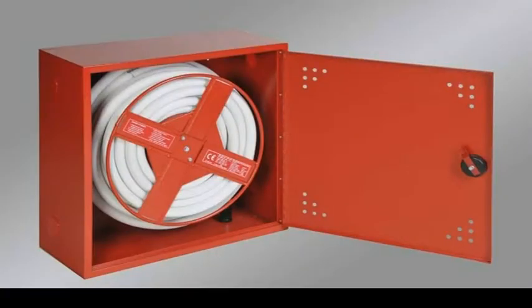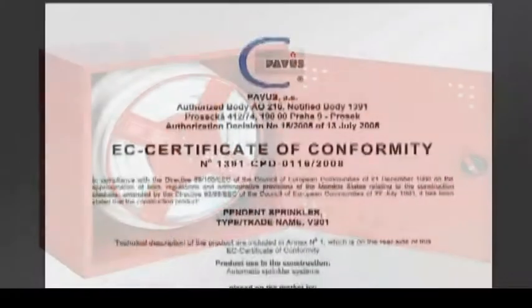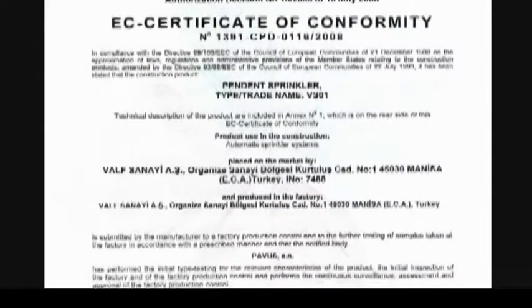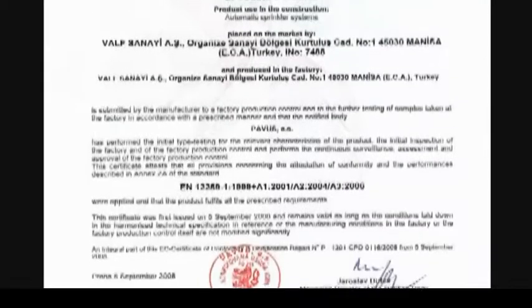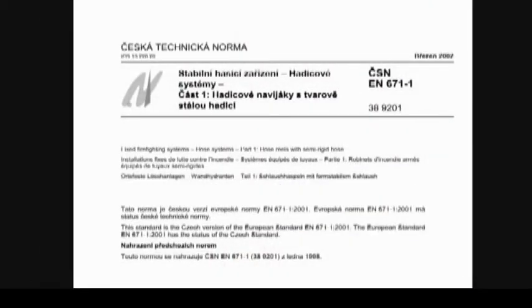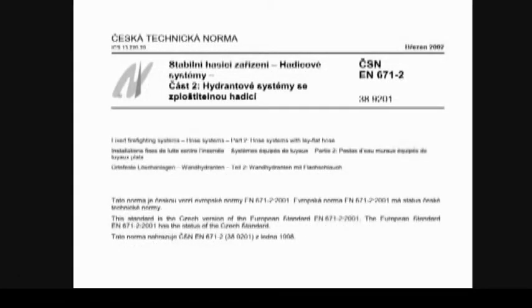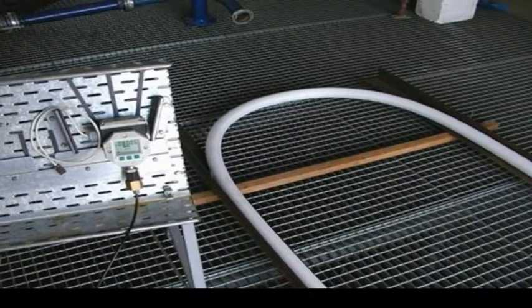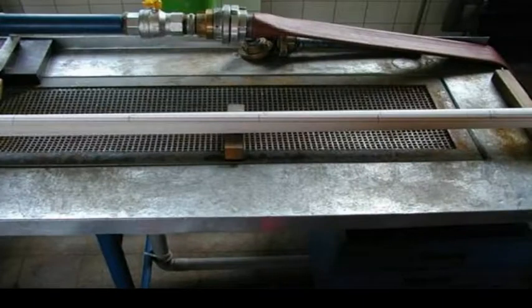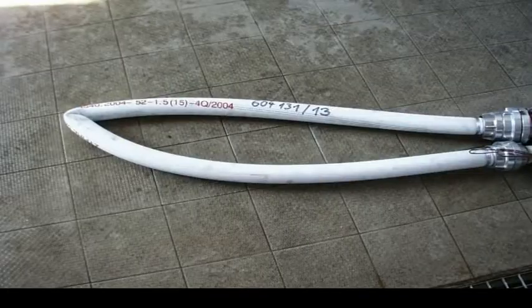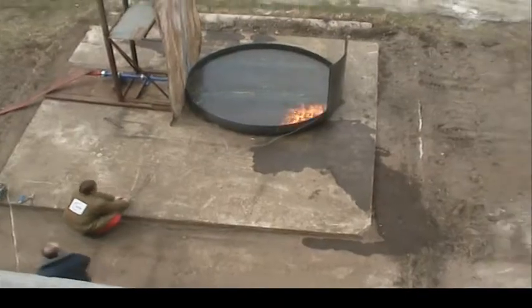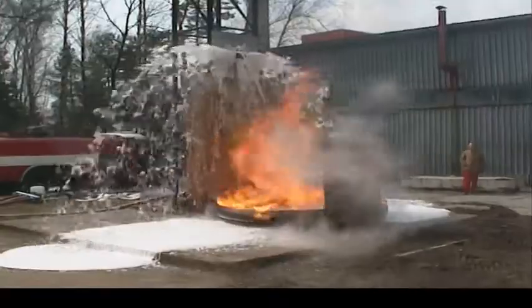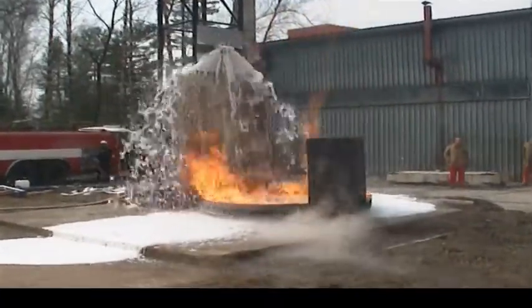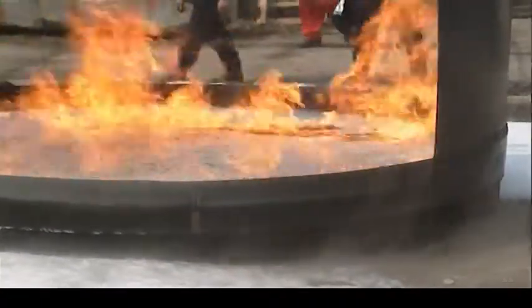In the initial type test of hose systems, both of semi-rigid hoses and of lay-flat hoses, test procedures complying with EN 671-1 or EN 671-2 are applied, with the assessment of the production control system, which leads to the conformity mark CE. In the type tests of fire hoses, test procedures according to European standards, Czech technical standards, or foreign standards are applied. An integral part of tests of extinguishing agents are their proper extinguishing abilities. Their characteristics are verified with foam compounds, as well as expansion ratio and half-time or quarter-time of foam decomposition.